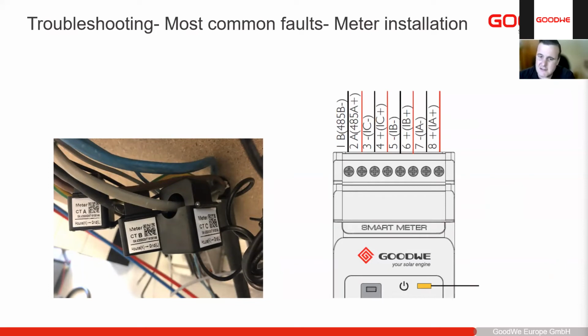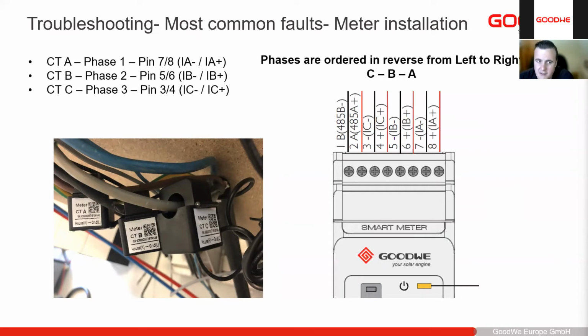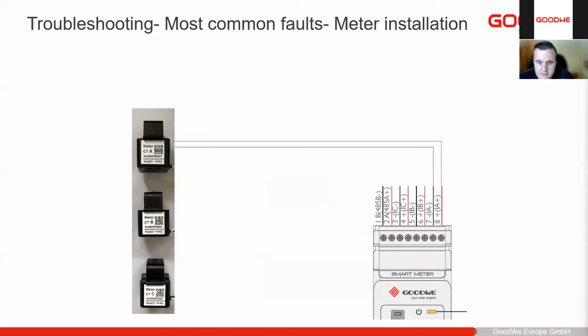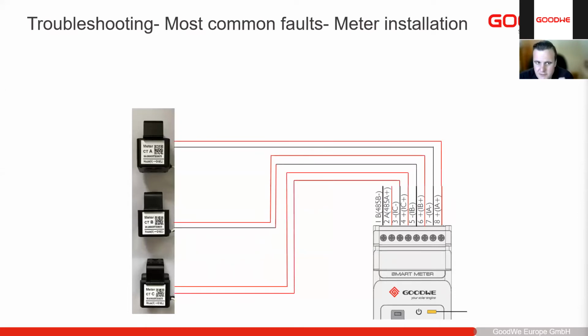Please pay careful attention to this wiring. This does happen sometimes, we do miss because A is here. A starts from right to left. So A, B, C. A meaning L1, B, L2, C, L3. So very often logic would dictate that L1 would be here and L3 would be here. So please pay careful attention to this to make sure that they are correct. So that's 1, 2, 3. CTA is on 7 and 8, CTB on 5 and 6, and CTC on 3 and 4.